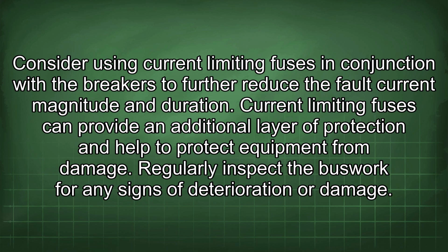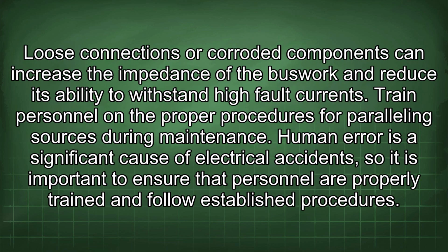Regularly inspect the buswork for any signs of deterioration or damage. Loose connections or corroded components can increase the impedance of the buswork and reduce its ability to withstand high fault currents. Train personnel on the proper procedures for paralleling sources during maintenance.